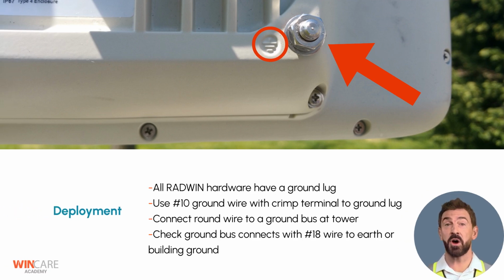All RADWIN hardware is equipped with a dedicated ground lug as indicated by red arrow, clearly marked with the electrical ground symbol as marked in red circle. This connector provides the primary grounding point for the radio's internal circuitry, safely redirecting electrical surges or static discharges away from the unit.